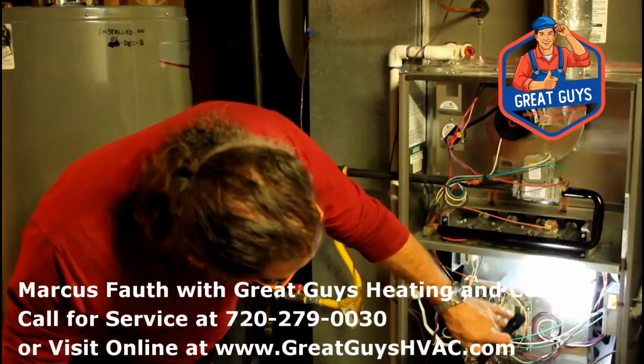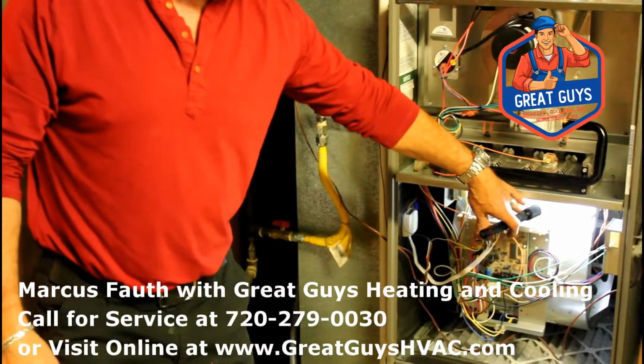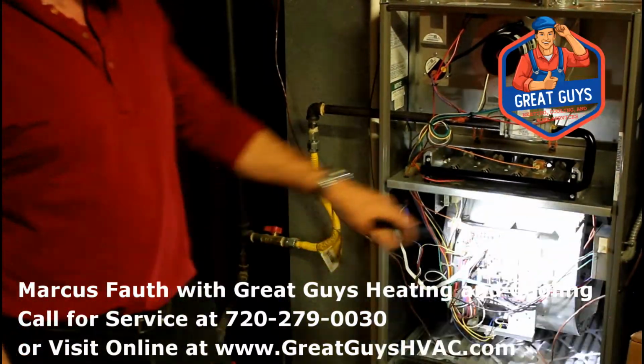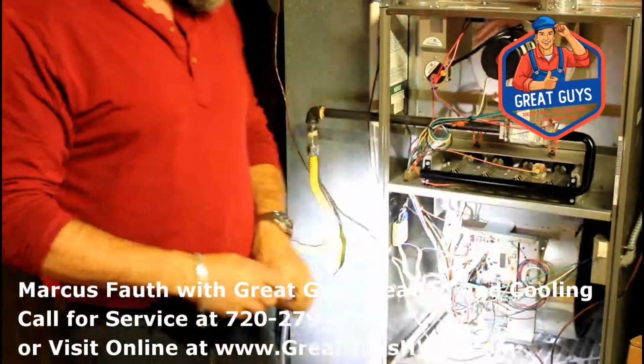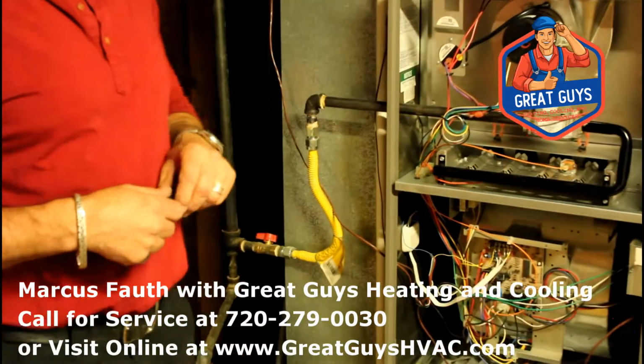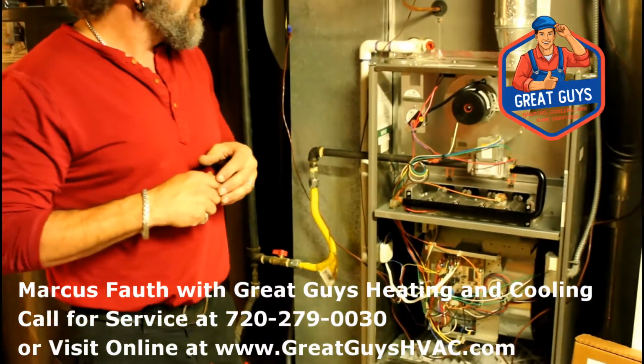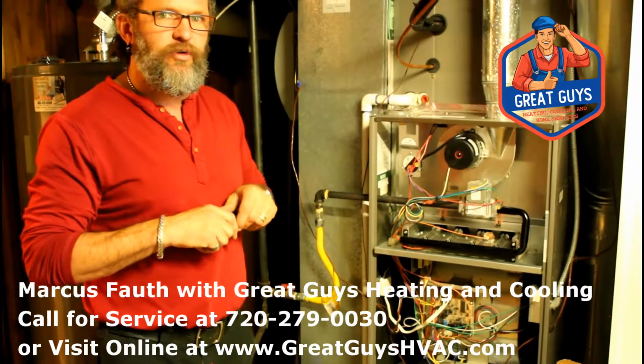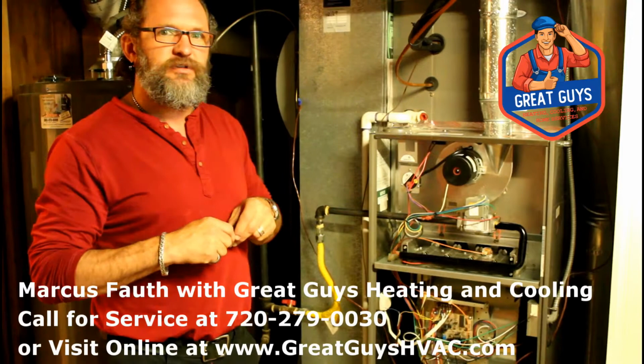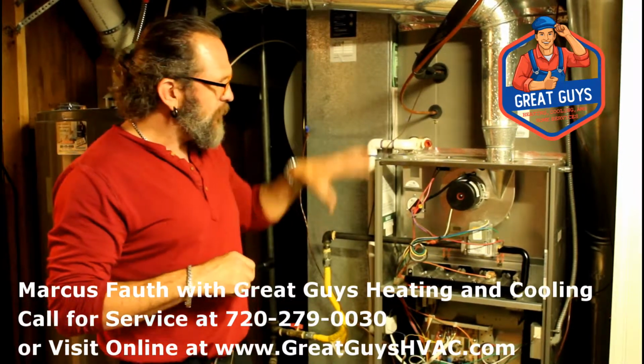I'm not sure if you can see down here in the lower section, there's what's called a blower motor capacitor. That obviously gets tested to manufacturer specifications, as do the relays, safeties, limits, controls, wire terminations, and blower door safety switch. All of those components are verified to be within manufacturer specifications. During our inspection, if anything that we test is out of specification, then we generally contact Jim or the property owner and go over those specific elements to recommend the repairs or replacements needed in order to keep the system operating as the manufacturer designed. That covers the basic furnace.